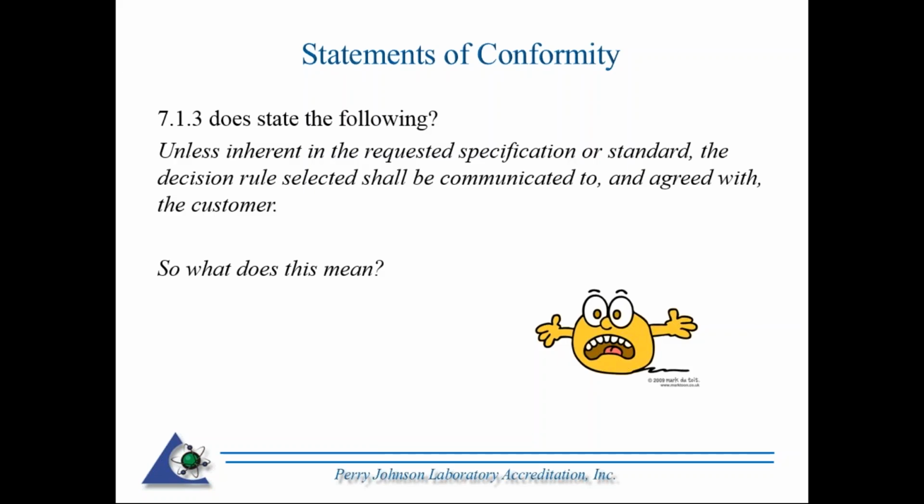So you may have noticed one there under 7.1.3, it said unless inherent in the requested specification or standard, the decision rule selected shall be communicated to and agreed with the customer. This is rarely seen where this was prevalent in the types of calibrations that I've been involved in. It is actually utilized a lot with those folks that are involved in testing laboratories. So what does this mean?